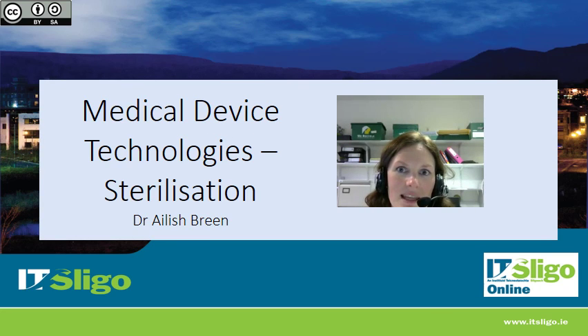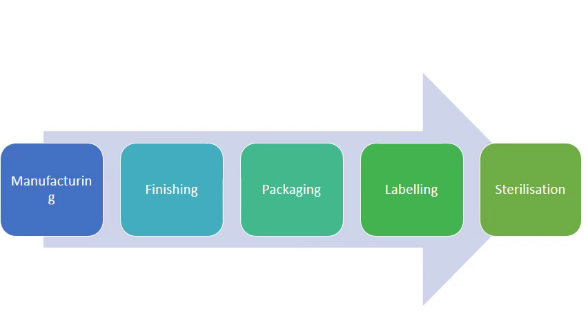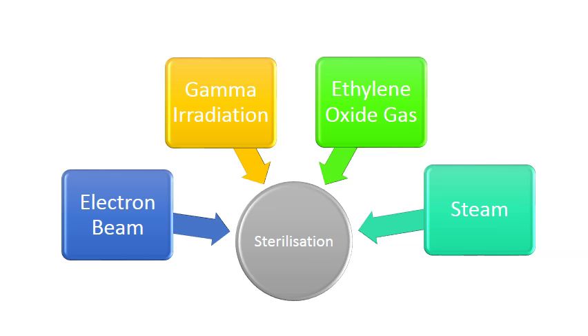Welcome back. At the end of the manufacturing process, sterilization is key, and the next few slides will talk about electron beam sterilization. Looking at the lifecycle of a medical device, it goes from manufacturing to finishing — polishing, grinding, electropolishing, passivation — then gets packaged, labeled, and the final activity in the chain is sterilization, which sees the product sterilized and ready to ship. The sterilization methods typically used in medical devices are electron beam, gamma radiation, ethylene oxide gas, and steam. We'll focus on the first three.